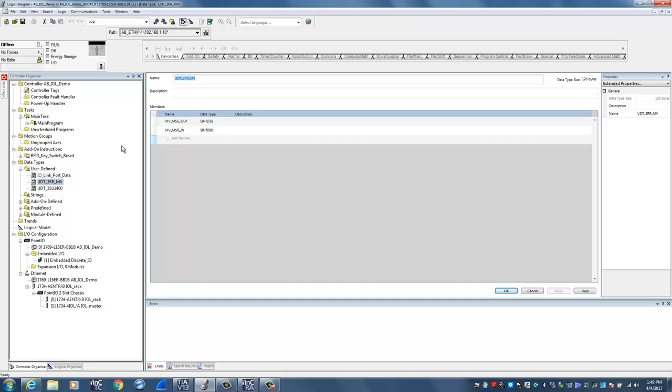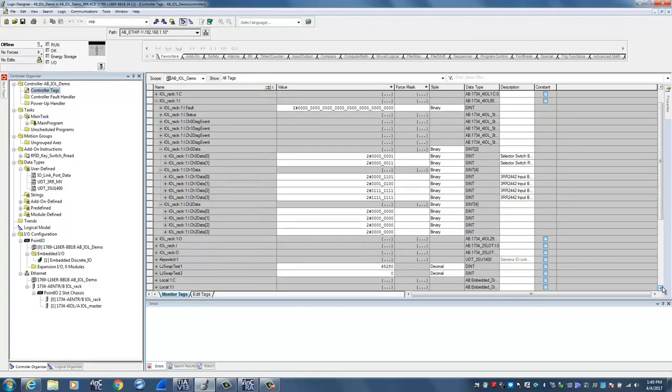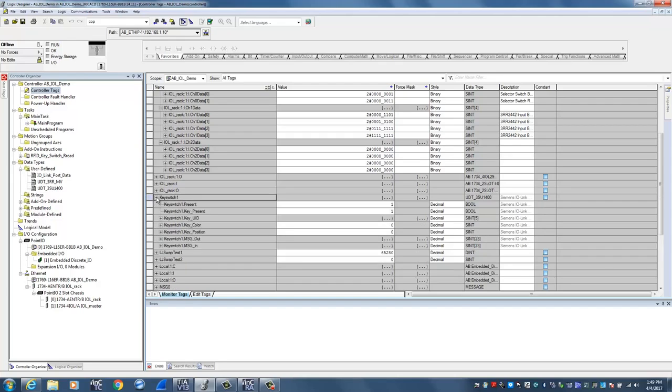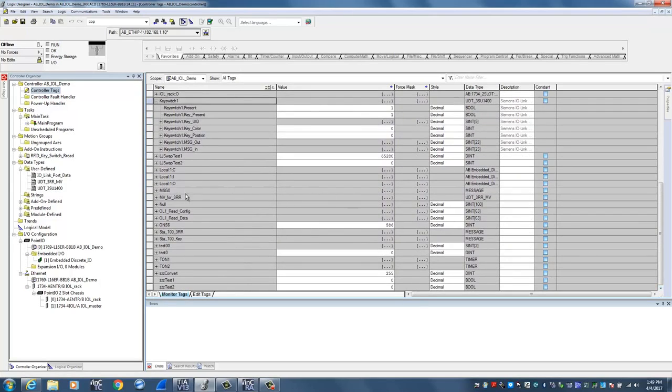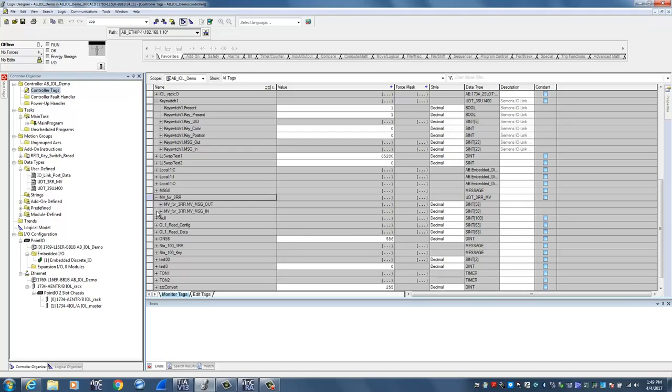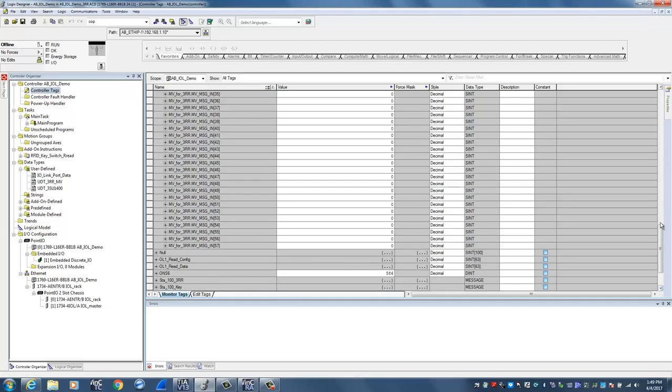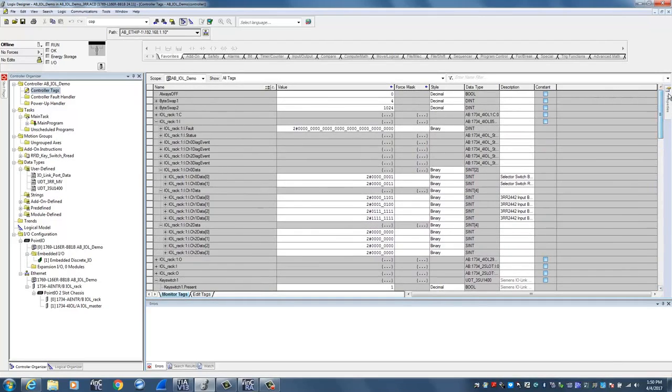Once you create the UDT, you then go back up to controller tags. And in this case for the RFID key switch, I created an additional tag called key switch, and if you expand that, you'll see that's the information set up from the UDT. And we also set up a second tag with the UDT for the monitoring relay. So if I come over here for MV_for_3RR, that tag, as you can see, is of type UDT_3RR_MV. And if I expand that, you'll see on the input and on the output 58 bytes of data and tags set up for that device as well. So that gives you the location where you can store and map the information coming from the device.